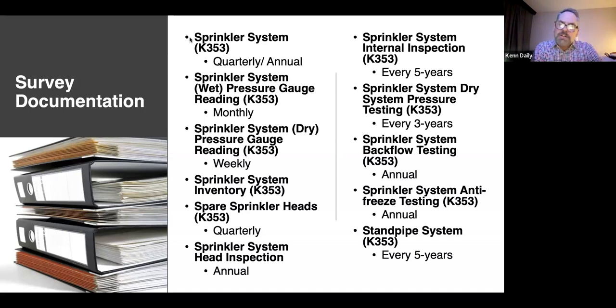And then your spare sprinkler inventory, which your sprinkler company should give you under NFPA 25. We're required to have an inventory of all the heads in our building, all the types that we're using in our facility, and the number of those heads. And once you have your number of heads, that drives the types of spares and the number of spares that you have in your building. I'm just recommending that you either quarterly or annually confirm your spares are being stored appropriately, that the wrench is still in the red box that goes with the spares, and that your spares are in good shape.